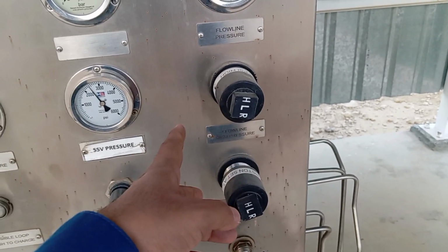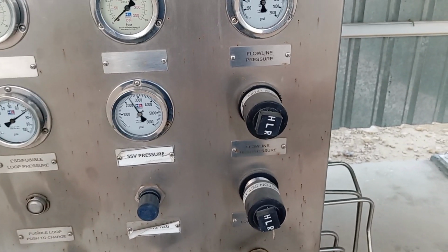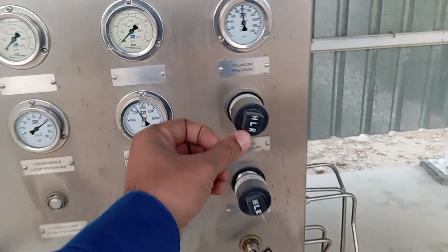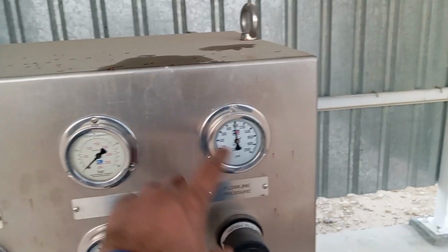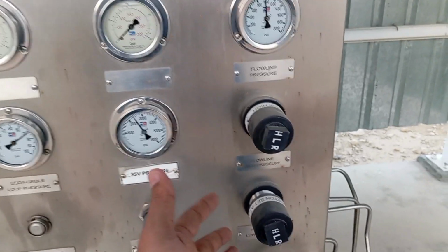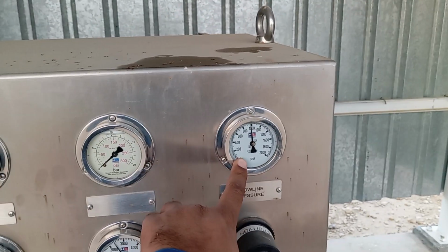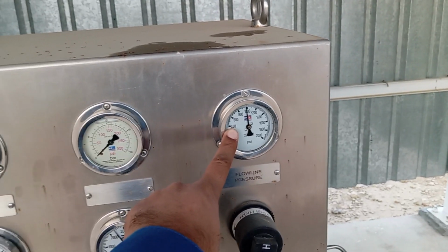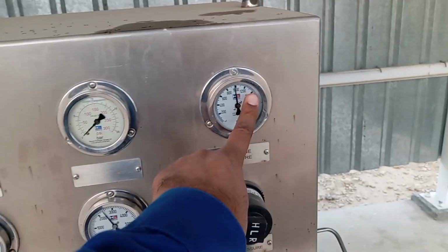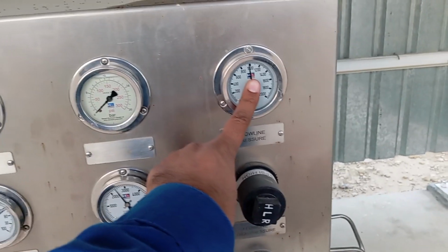And then third we have the flow line pressure. High and low pilot switches monitor the flow line pressure. In case of leakage, the low pilot switch will operate, and in case of blockage, the high pilot switch will operate. In case of low pilot, both double SV and triple SV will shut down, and in case of high pilot, just the double SV will shut down and the triple SV will remain open. The process team gives you the set points for these high and low pilot switches. In this wellhead control panel, low pilot will operate at 400 psi and high pilot will operate at 1250 psi pressure.